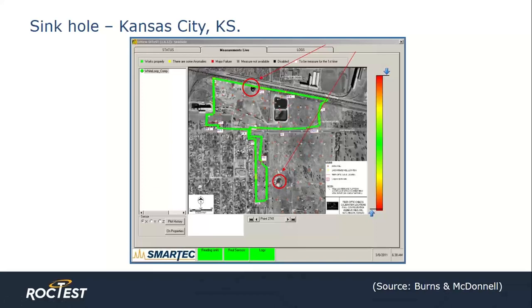This is a screenshot of the user interface. The limits of the monitoring zone are outlined in green. The DiveView software sends alerts if cable deformation exceeds the alarm levels set by the client. Alerts are sent by email and text message to key personnel, including the City Fire Department. If there is no acknowledgment of the alert, DiveView automatically sends reminders until that alert is acknowledged. In the graphic you can see the residential subdivision to the lower left, the rail line across the top, and the salt extraction wells throughout the center as red dots. Called out at the top and bottom are the sinkholes found.